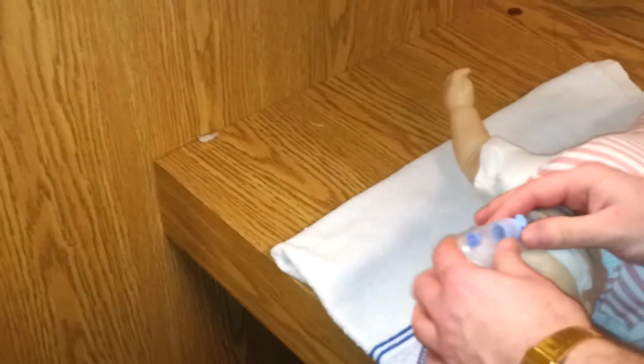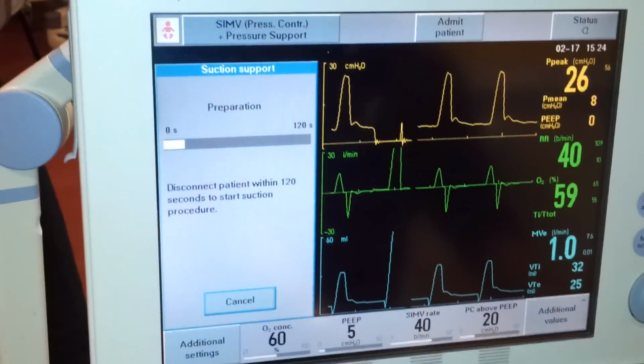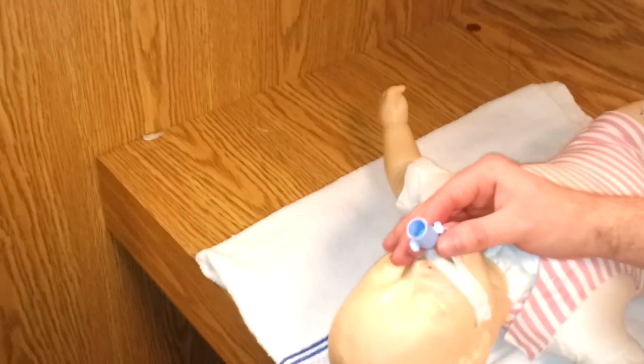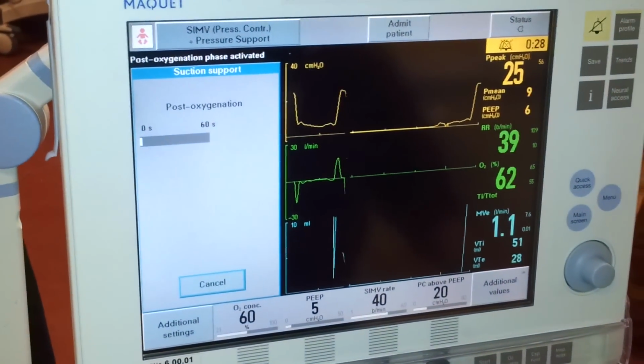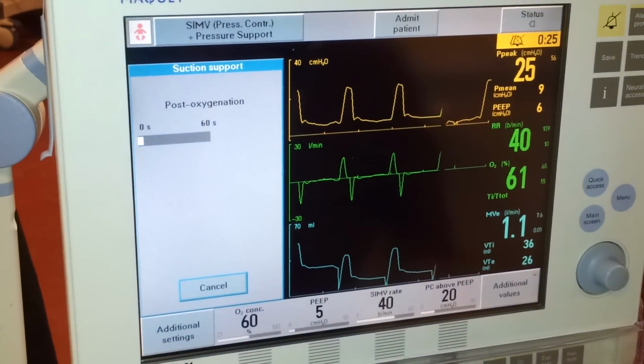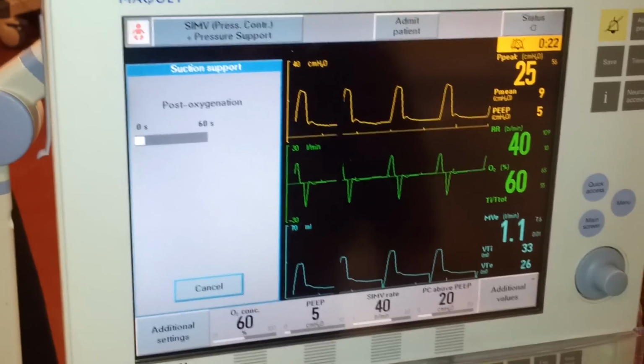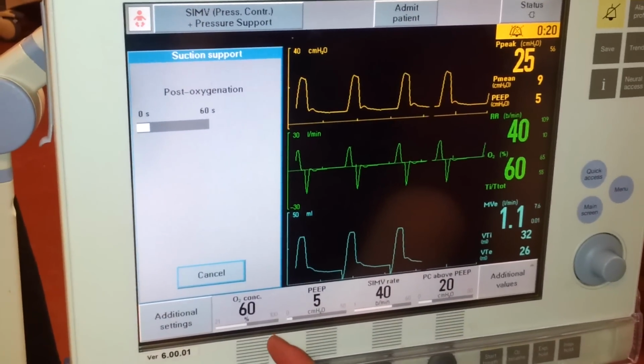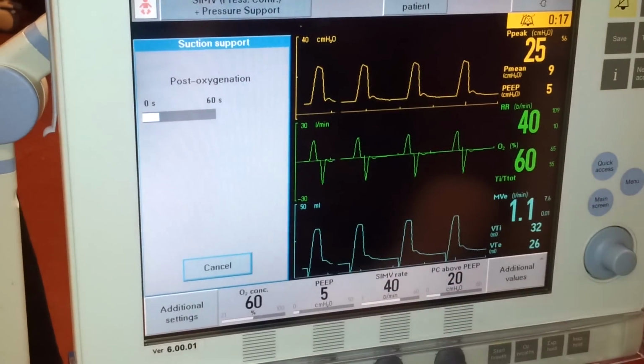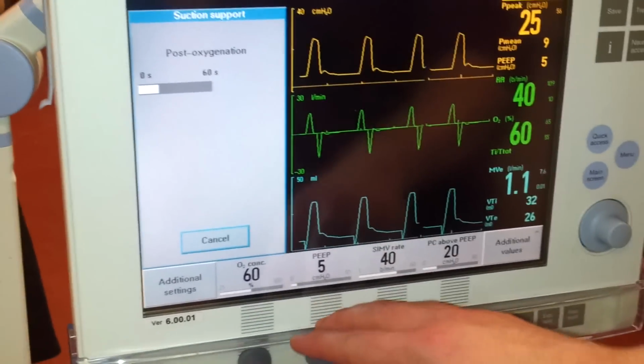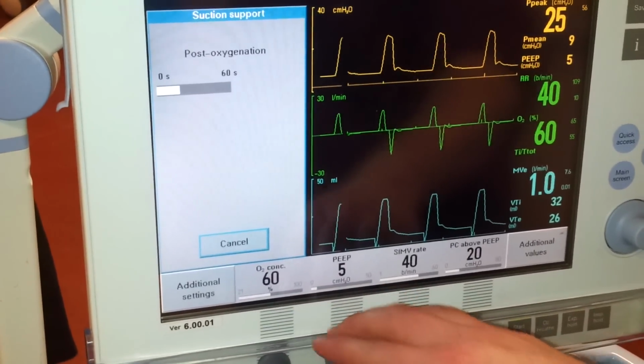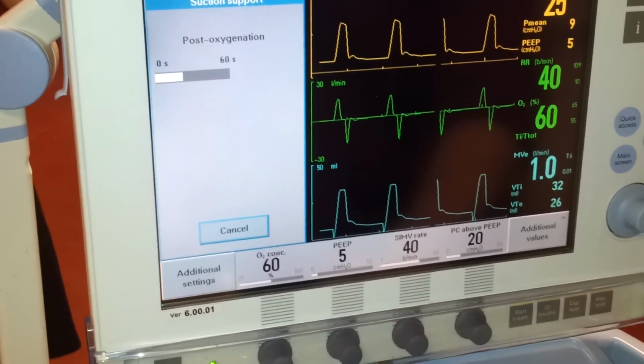When you disconnect the baby from the ventilator, it will go to standby. And at this point you can suction the baby, and when you're done you reconnect, and now the ventilator automatically goes into post-oxygenation or re-oxygenation, and it goes to that same FiO2 that you set, and it'll give it for 60 seconds. If that 60 seconds runs out and you're still on that increased FiO2, it will go back to the original FiO2 you had set. So at this point we're just going to cancel that.